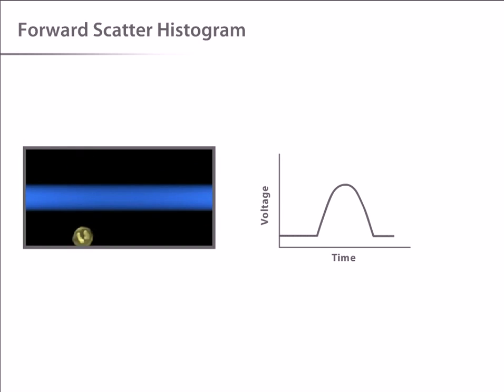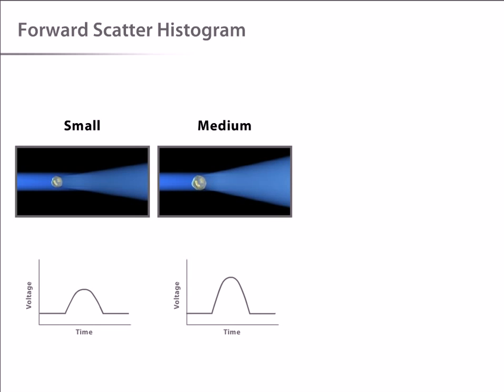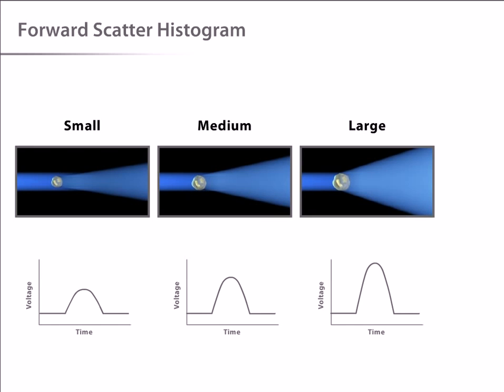The scattered light received by the detector is translated into a voltage pulse. Because small cells produce a small amount of forward scatter and large cells produce a large amount of forward scatter, the magnitude of the voltage pulse recorded for each cell is proportional to the cell size.